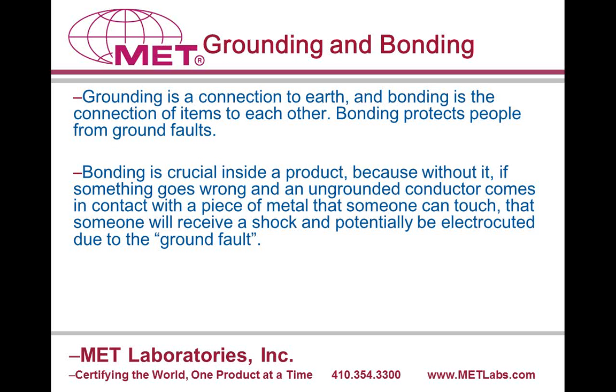I want to take a few minutes to talk about grounding and bonding. Grounding is your connection to the earth line, and bonding is your connection between all of the metal of the system that's not insulated to that line and to each other. Bonding is absolutely critical in preventing electric shock because it prevents the metal enclosure from becoming live if something becomes loose inside of your equipment.